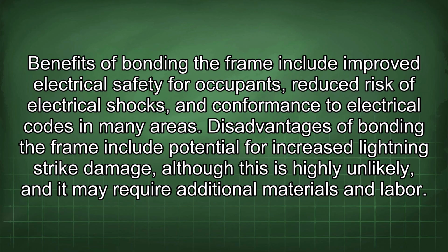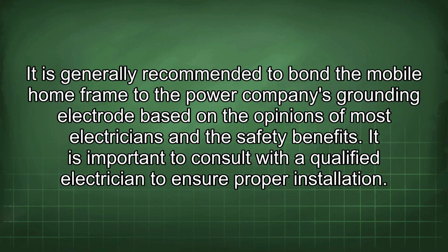Benefits of bonding the frame include improved electrical safety for occupants, reduced risk of electrical shocks, and conformance to electrical codes in many areas. Disadvantages of bonding the frame include potential for increased lightning strike damage, although this is highly unlikely, and it may require additional materials and labor. It is generally recommended to bond the mobile home frame to the power company's grounding electrode based on the opinions of most electricians and the safety benefits. It is important to consult with a qualified electrician to ensure proper installation.